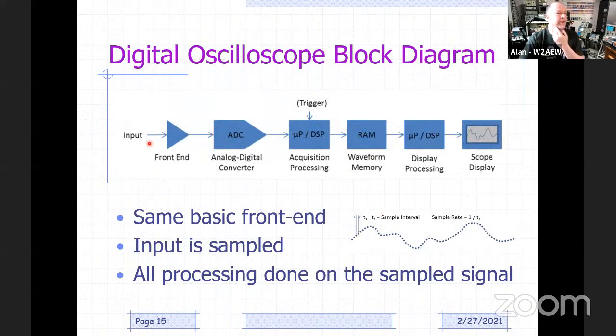So here's a simple, very simplified block diagram of a digital scope. Now it's the same basic front end, right? We're still going to have input attenuator, input preamps, and things like that. But rather than going off and applying that to a vertical amplifier to drive deflection plates, we're applying that signal into an analog to digital converter, which is basically taking samples of that waveform, okay, and sending those samples off to be processed. The trigger system will be looking at it. In some scopes, the trigger system will be looking at the digital samples. In some cases, the trigger system might be pulling data off of the analog input. It all depends on the scope.